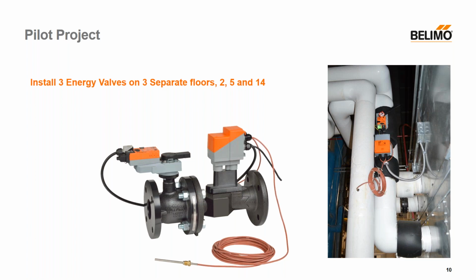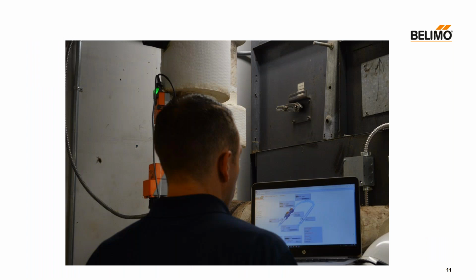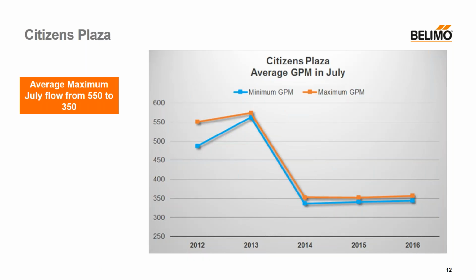We did regular downloads of data on a scheduled basis, and we took all of this data so that we could track the progress and really show and prove the energy savings and what we were telling them. And that initial pilot project showed a savings of nearly 280,000 gallons of water, which thankfully led to, in 2015, a retrofit of the entire building. And that caused a 49% reduction in chilled water pumping and an average savings of $23,000 in chilled water savings.